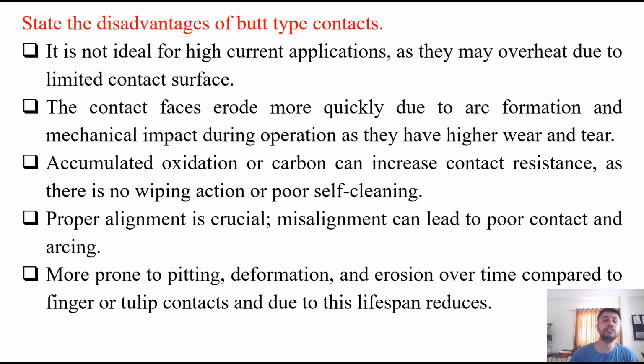The disadvantages of butt type contacts. So there are limitations of butt type contacts, some of which we are discussing right now. It is not ideal for high current applications as they may overheat due to limited contact surface area, and also we have mentioned that these contacts are used for low and medium voltage circuit breakers, so the current carrying capacity of the contacts is limited.